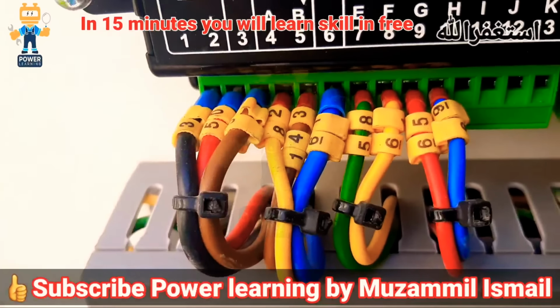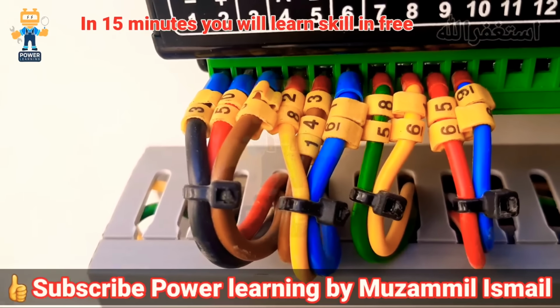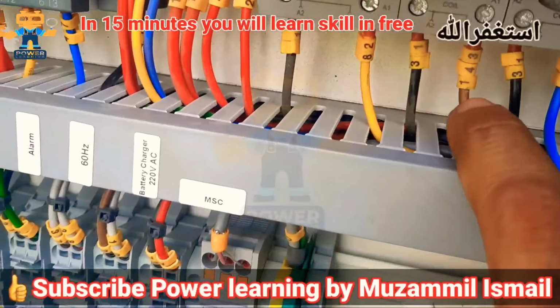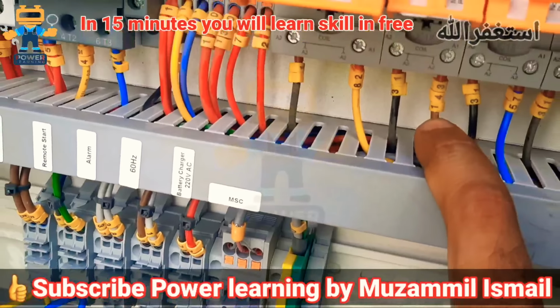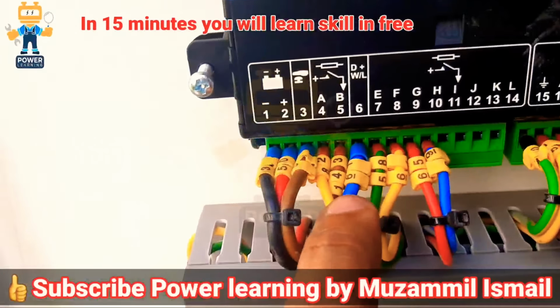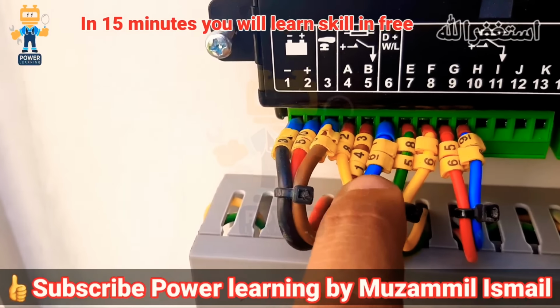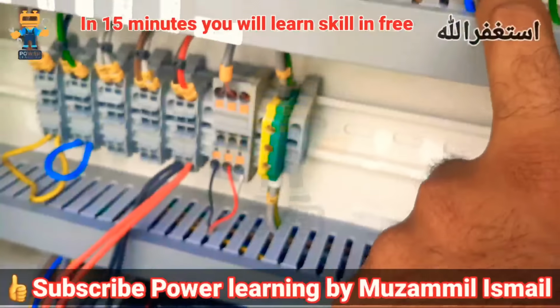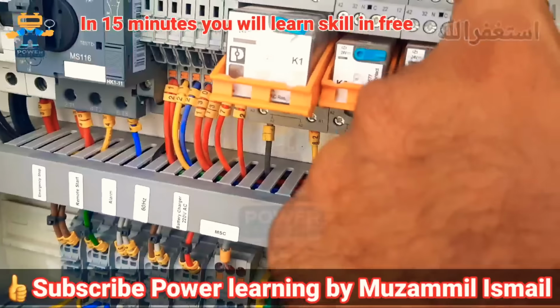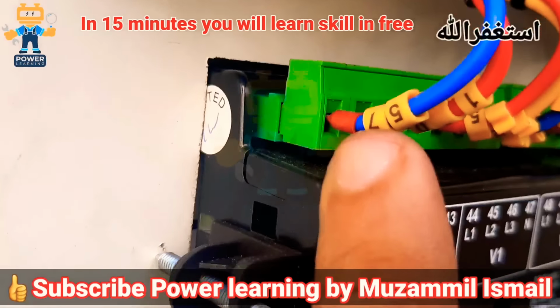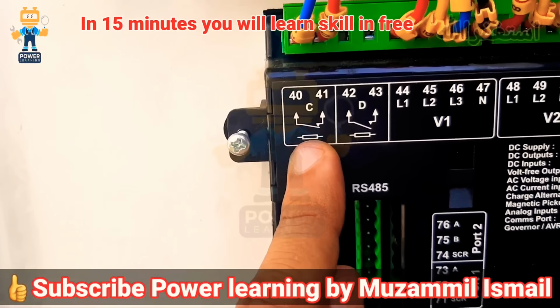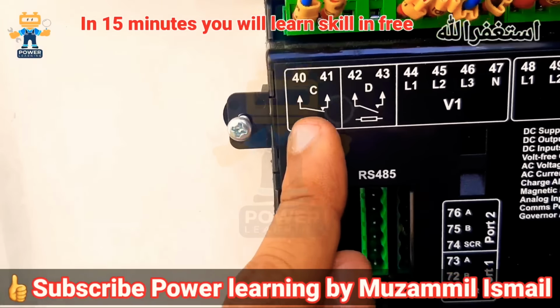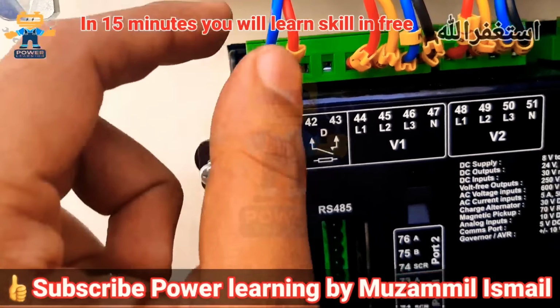If you see, this 82 wire is connected here, yellow color, on the fuel. After that, here we have 143 for the starter relay. It is also connected here on the digital output 143. The next relay is 57, which is gen contact relay 57. If you see here, this is 57. And this is a volt free contact, which is closing our contactor. Normally close contact we are using here.